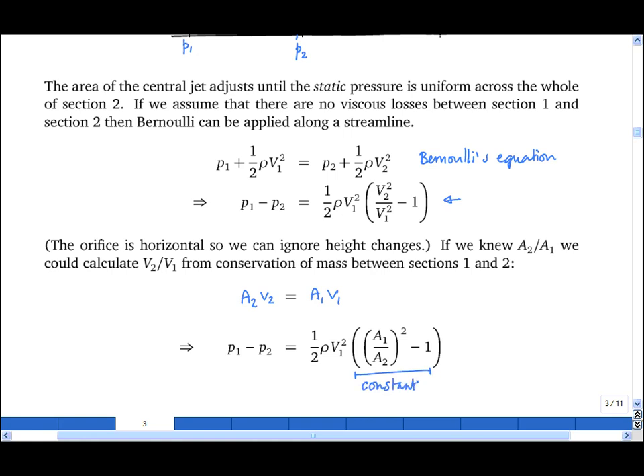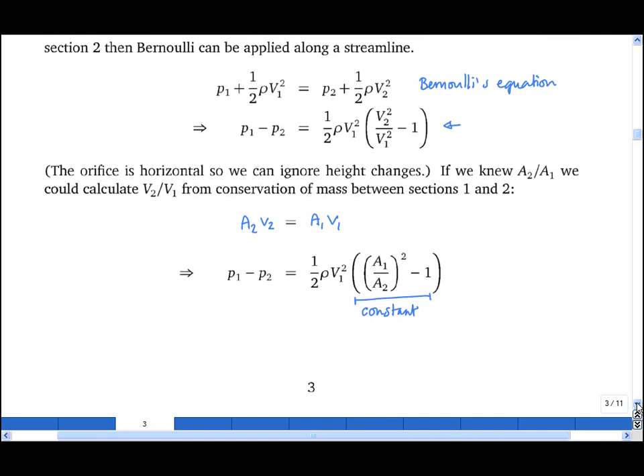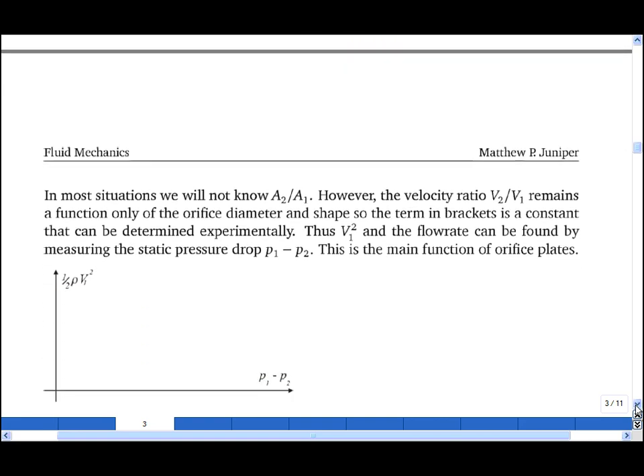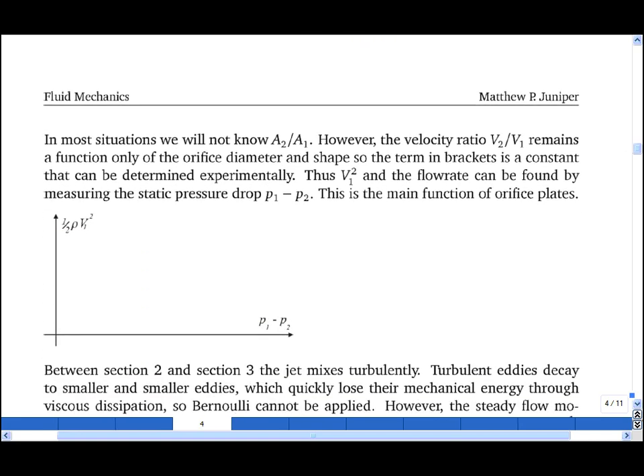Now in most situations we won't know A1 over A2. However, this is a constant that can be measured experimentally. And so to calibrate our orifice plate, we conduct a set of experiments in which we set V1, and then measure P1 minus P2, and then we plot P1 minus P2 against a half rho V1 squared. Once we've calibrated the orifice plate, we can then measure P1 minus P2 in order to work out what V1 is going through the pipe.